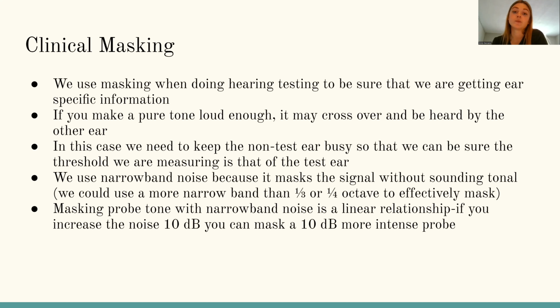But when we're playing something really loud in one ear, we have to make sure we're keeping the other ear busy, so that when we're playing the loud sounds in the ear with hearing loss, we can know that we're actually getting a response from that ear and we're not measuring any response from sound that has crossed over to the other ear. So yeah, we have to use masking to cover up that tone and keep the other ear busy so that we're not testing that.